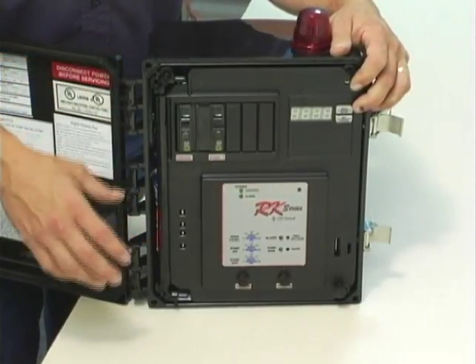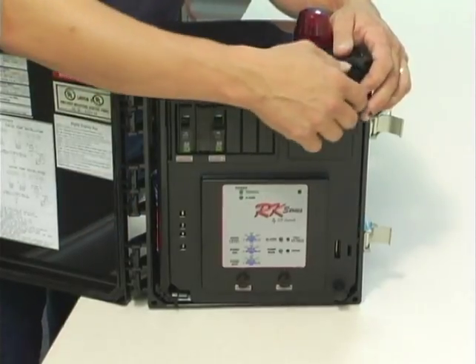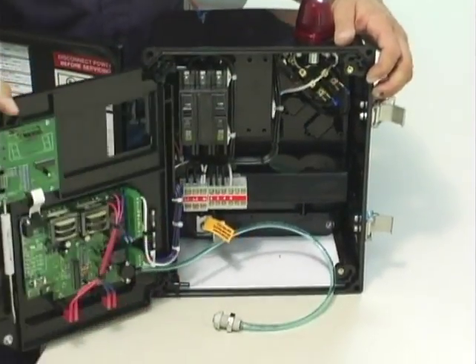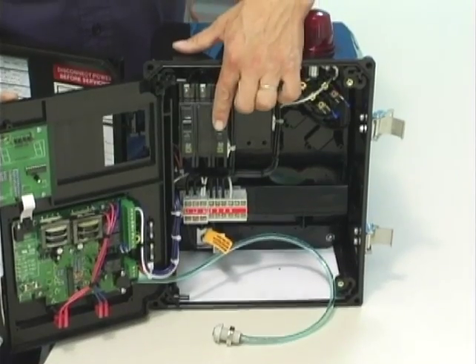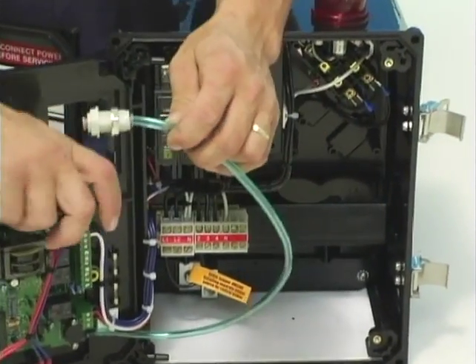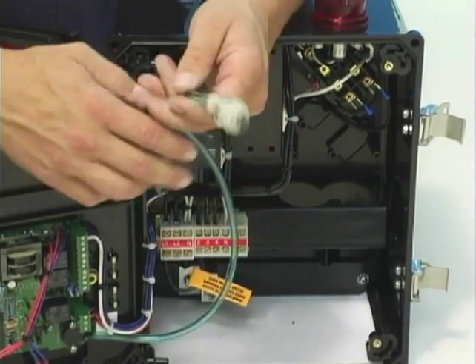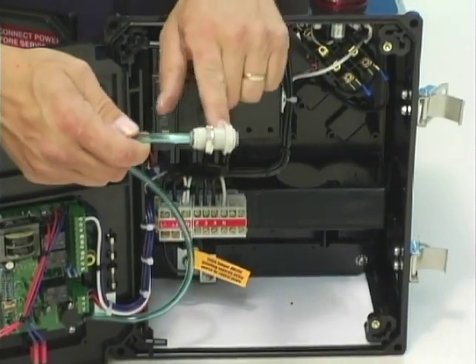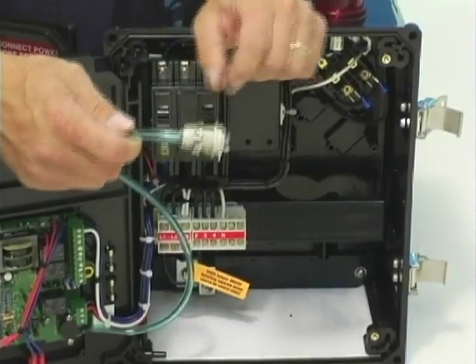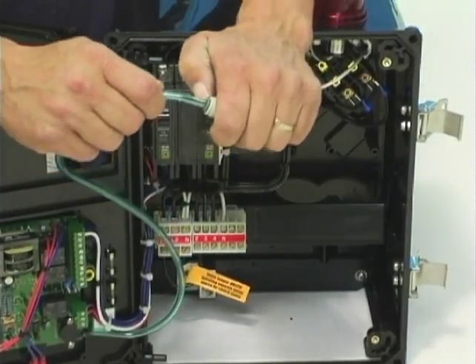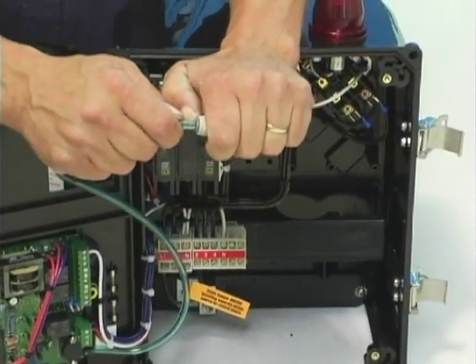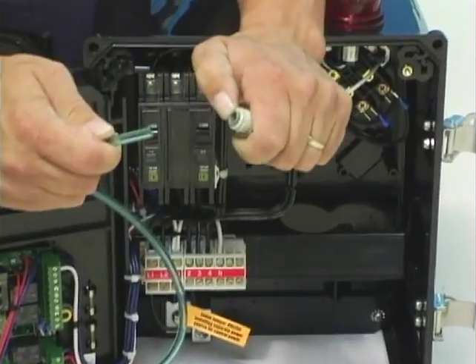If there is water in the tank, you'll need to remove the pressure bell out of the tank, open the door of the control panel. You'll turn the control circuit breaker and the pump circuit breaker off. You'll take the coupling, and in order to open the airline, take the airline apart, you'll need to squeeze inward on this gray coupling and slide the tubing out.